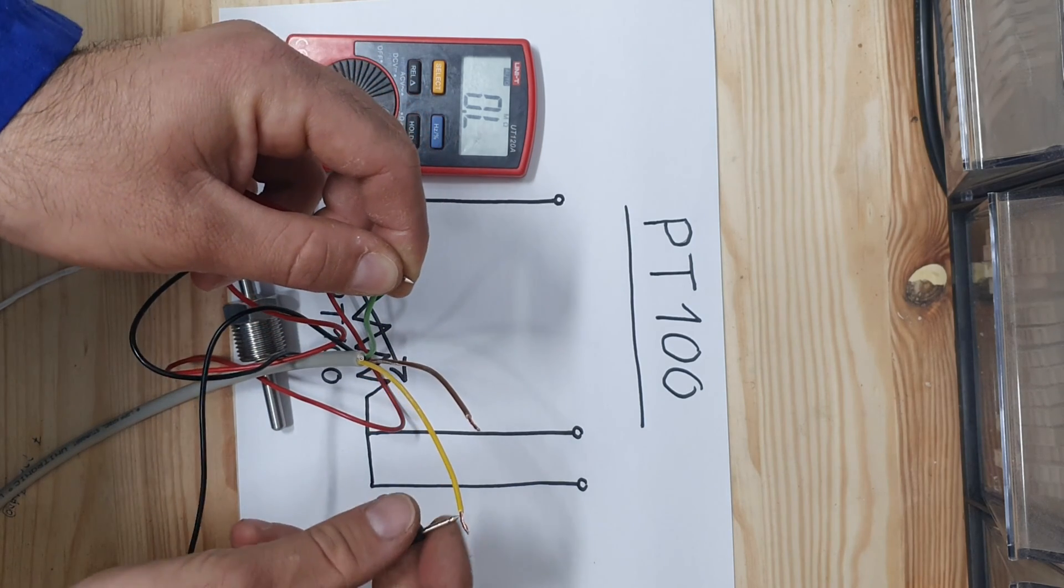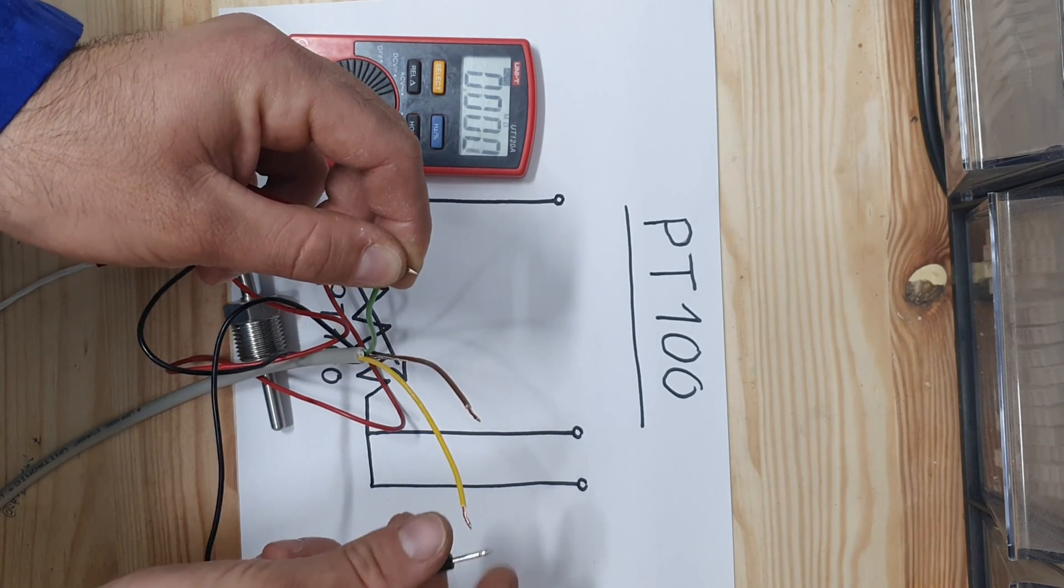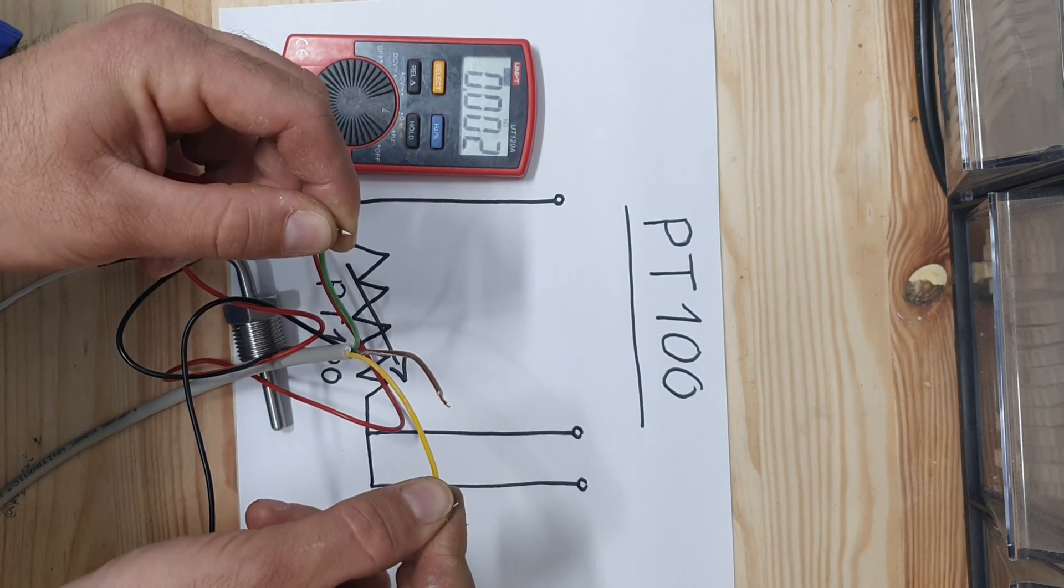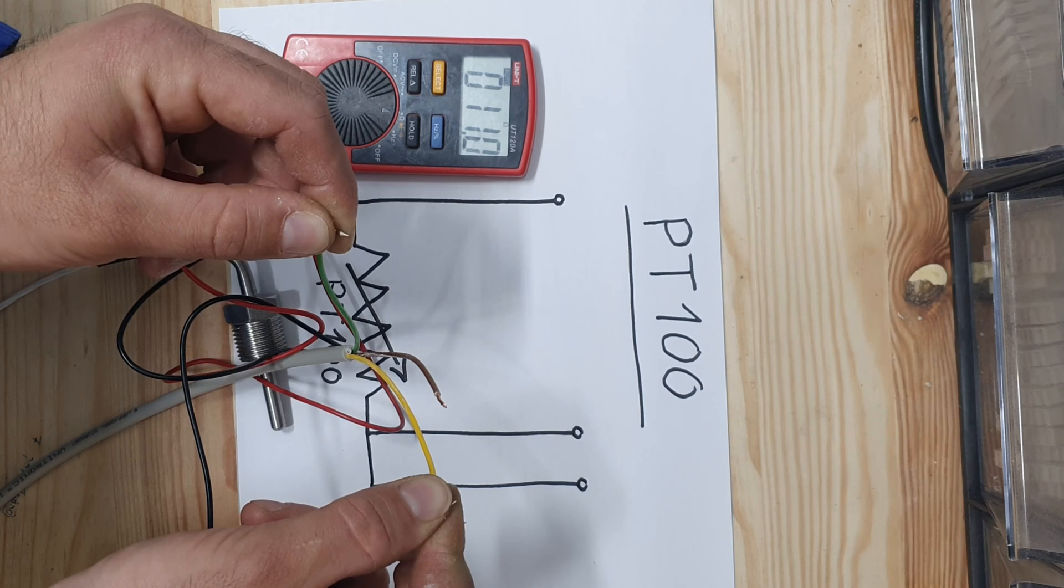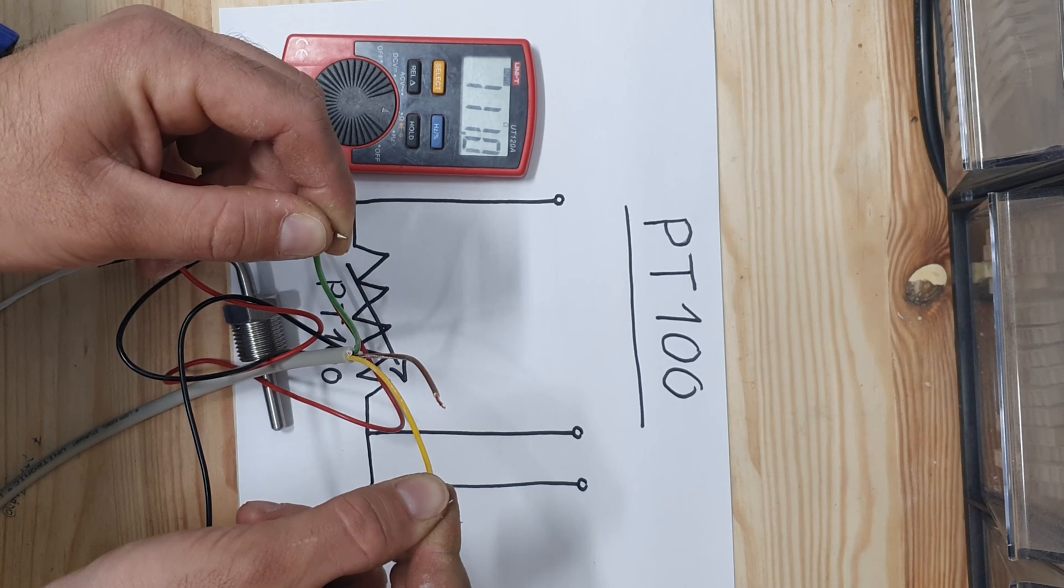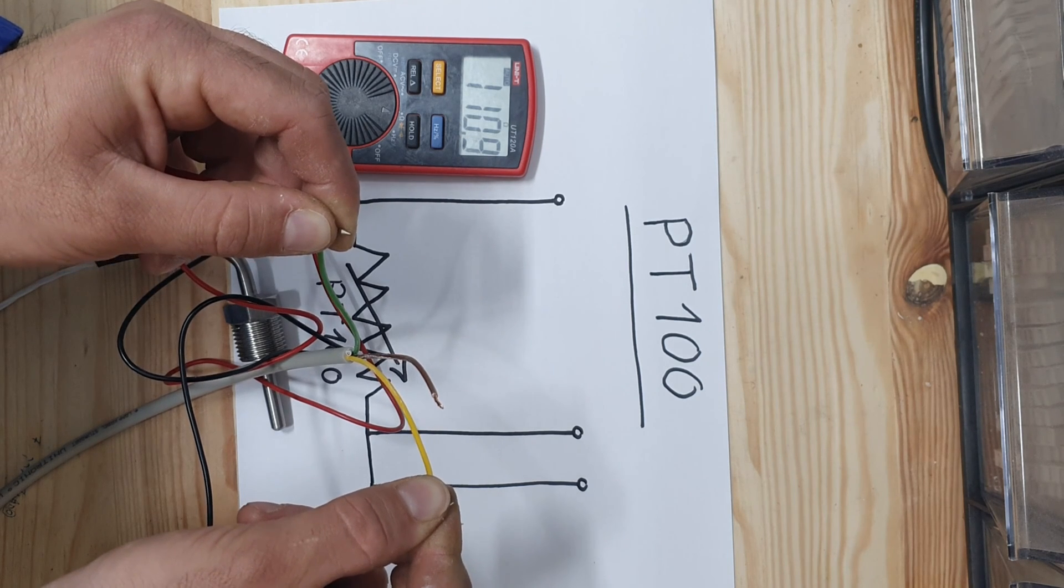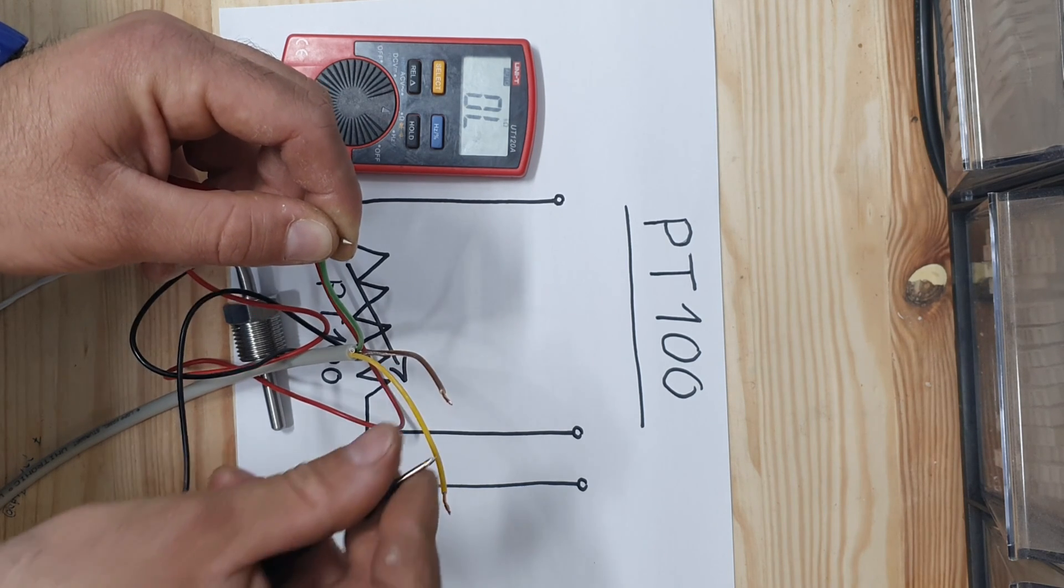Measure the resistance between each couple of wires. You have to get a reading close to 100 in two couples and zero in one couple.